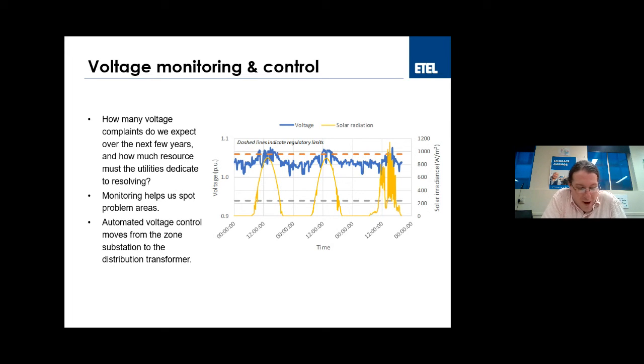Now, this is one example where we can see a saving in monitoring. If the utility gets a voltage complaint, then they'll probably have to dispatch somebody to connect up monitoring to the transformer or to the site, and then decide what to do about it. If there were monitoring on the transformer already, then they can download the data, and that has saved one trip out to set everything up. And of course, if they install a monitor, they might have to collect it at some future date, so they have to send somebody out again. As I mentioned, the cost saving does depend on how far the person has to drive, but we do see that it can be quite significant.